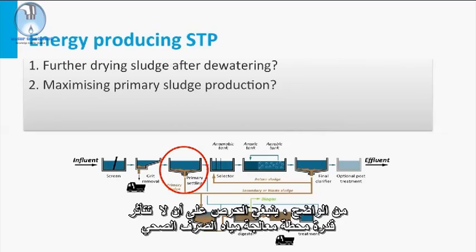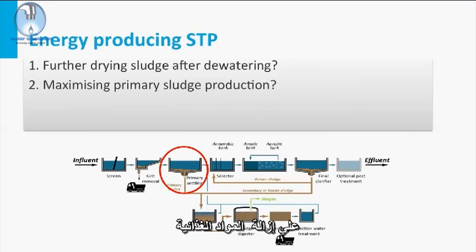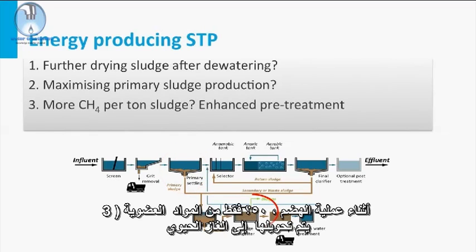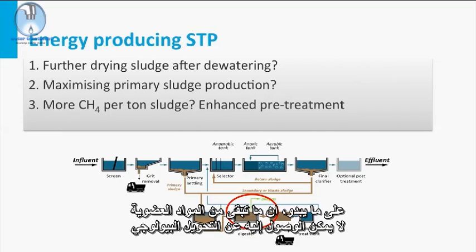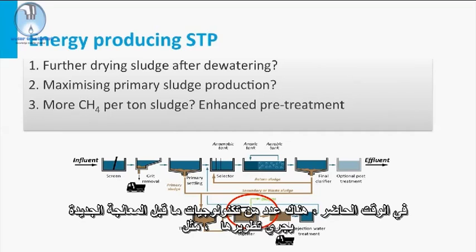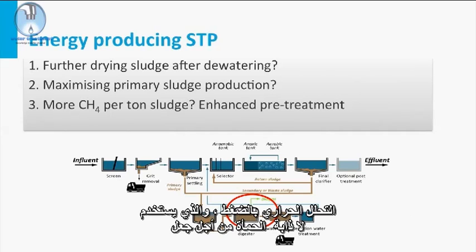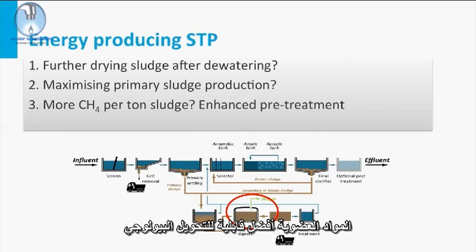Obviously, care should be taken that the nutrient removal capacity of a sewage treatment plant will not be affected. Third, during digestion, only 50% of organic matter is converted into biogas. Apparently, the remainder of the organic matter is not accessible for bioconversion. At present, a number of novel pre-treatment technologies are being developed, such as thermal pressure hydrolysis, which is used to solubilize the sludge in order to make the organic matter better accessible for bioconversion.